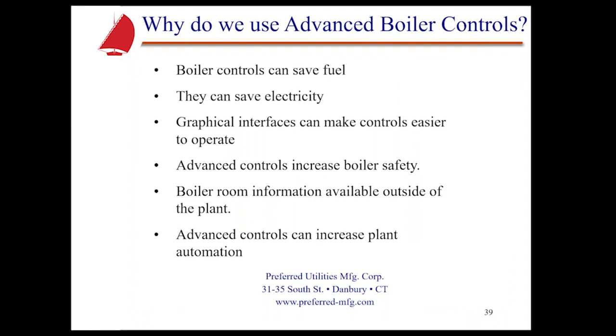So just a quick review. Our boiler controls can save fuel. That's a primary need right there. They can save electricity. The graphical interfaces can make the controls easier to operate. The advanced controls actually increase the boiler safety, and that's a big deal. Boiler room information can be available outside that plant. That's where the communications come in, and sharing that information through communications to a building management system. And we can increase the plant automation, requiring less operator interface. It can be taken care of and operated more efficiently that way most of the time.